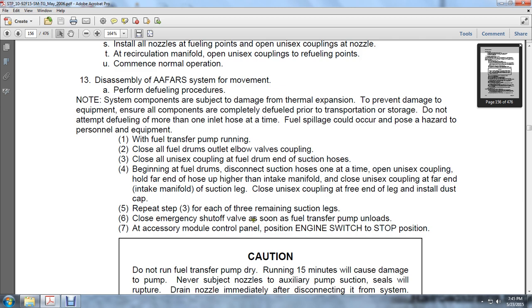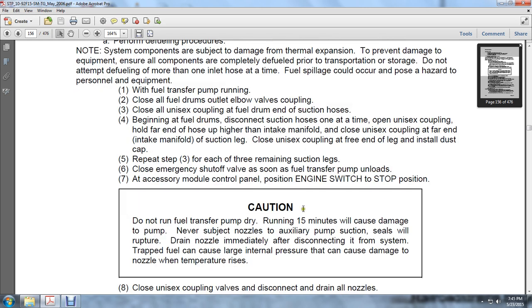Close the emergency shutoff valve as soon as the fuel transfer pump is unloaded. At the accessory module control panel, position the engine switch to the stop position. Caution: do not run the fuel transfer pump dry. Running it dry for 15 minutes will cause damage to the pump.